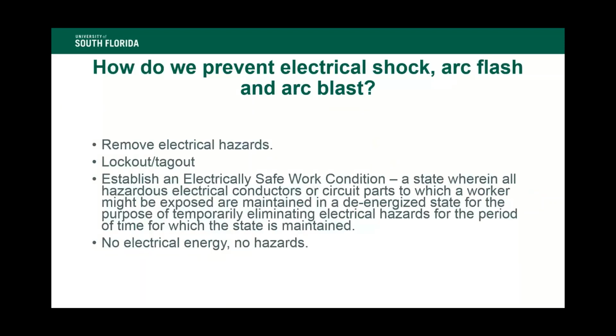So how do we prevent electrical shock and arc flashes and arc blasts? Well, we can remove electrical hazards from the picture. If we're getting ready to work on a piece of equipment, do we have to work on it hot or energized? Or can we do whatever we have to do in a de-energized state? We want to do everything in a de-energized state, but there are situations where that may not be possible, which we'll talk about a little bit later. We can remove electrical hazards by implementing a lockout tagout procedure, or we could establish an electrical safe working condition, which really isn't a procedure or a process as much as it is a state.